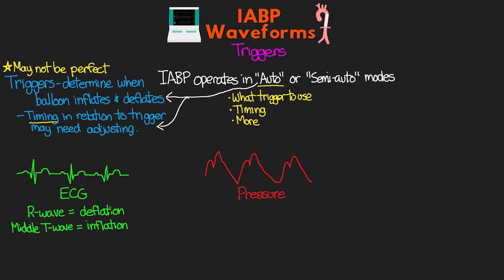The other trigger we have is the pressure trigger. In pressure mode, the balloon pump attempts to trigger inflation and deflation based on the pressures it reads. You'll actually see part of the arterial pressure waveform grayed out, showing that the balloon pump is recognizing parts of the waveform. You'll also see the heart rate indicator in the top right turn red. The trigger for inflation is the dicrotic notch on the arterial pressure, and the trigger for deflation is the start of the systolic upstroke.